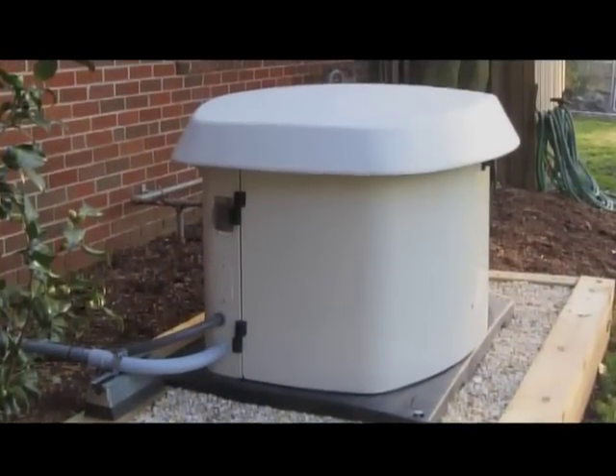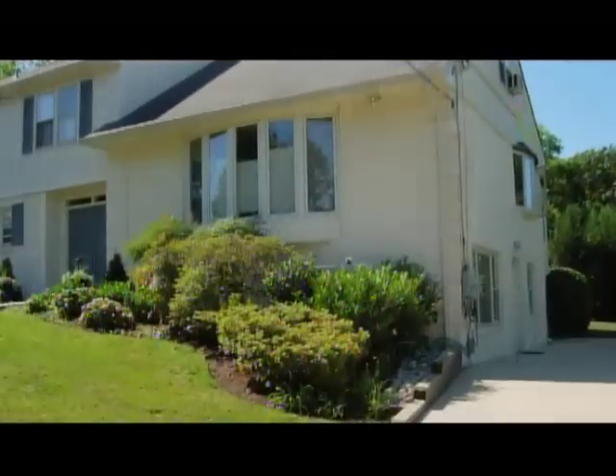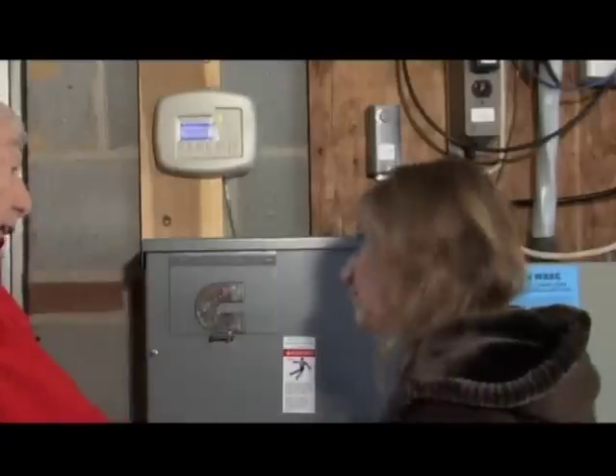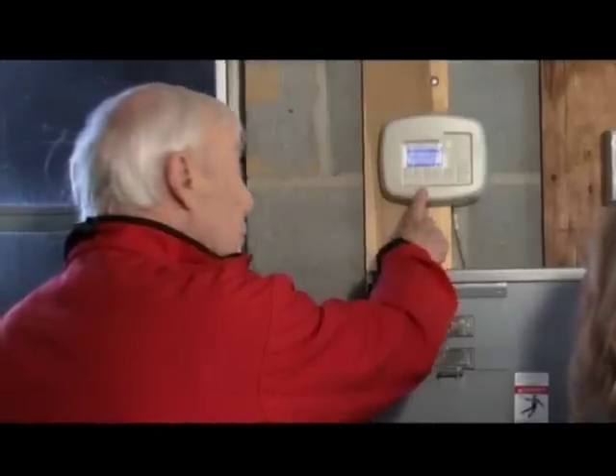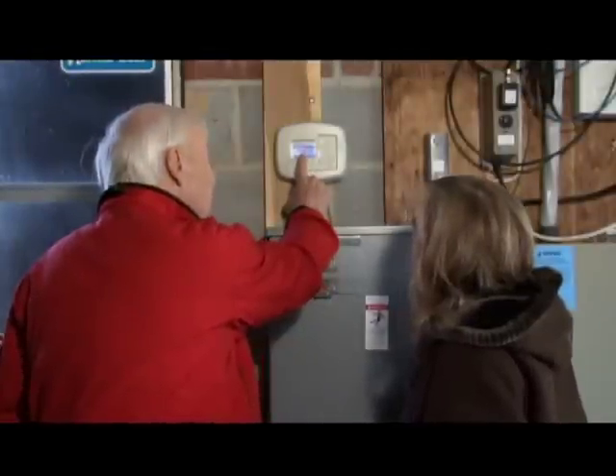This homeowner selected their generator, a Cummins-Onan RS20A. One important decision was deciding where to install it. There are two predominant influences when making that decision: the first is zoning laws, and the second is the integration with their landscaping and architecture, and the impact it will have on neighbors. Back inside the house, Bob describes many of the features on the control panel. We have an automatic transfer switch, and it also has an exerciser clock — we set it to exercise once a week without load. It also has a battery charger to keep the battery charged. This is a remote control panel unique to Onan. It tells you when it needs service, if there was a fault, and what was the cause of it.